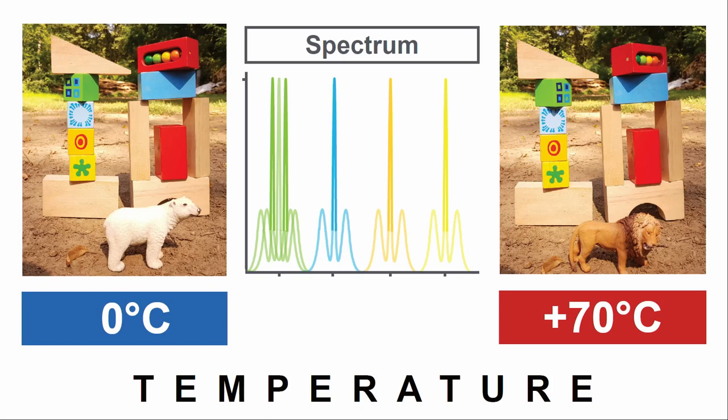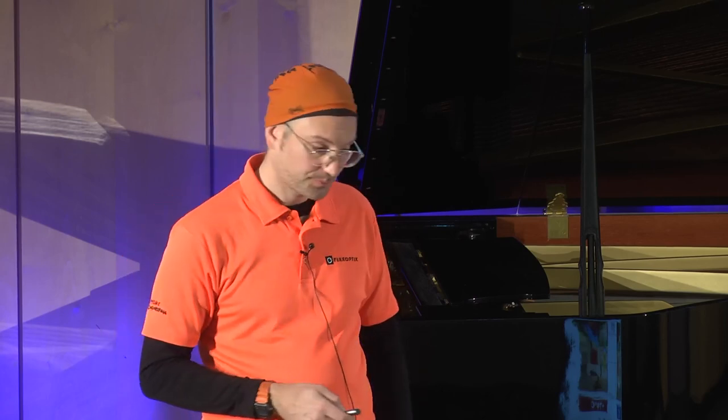The same, what we're gonna do is we heat it up within 60 seconds to 70 degrees centigrade coming from 0 degrees, really to the hot area, and also do the same measurement there to see how long it takes, or give a threshold there, until the lasers are going to be stabilized again. And that's a totally different test you do there. At the end of the day, it's a temperature test, but either taking the time in consideration or not. I think this is an important way to know if you do testing, do it the right way to get a proper result, because otherwise you will end up in failure parts at the end of the day.